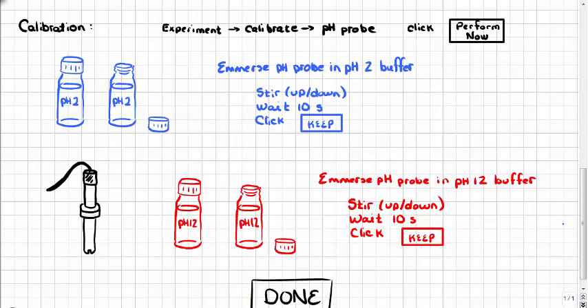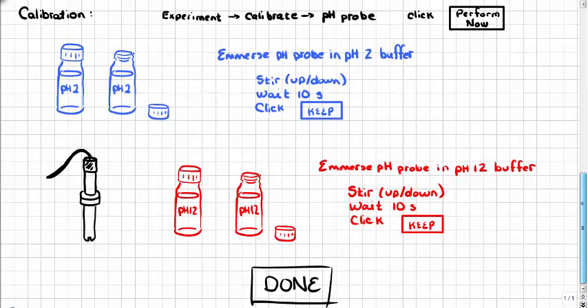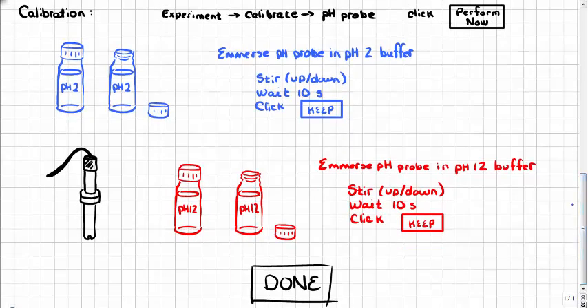They do need to be calibrated, and we're going to be calibrating the pH probes today using two different buffers of known pH. The first buffer is going to be a pH 2 buffer solution, and the second buffer is going to be a pH 12 buffer solution.